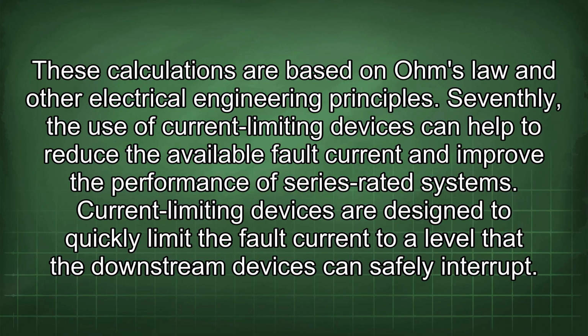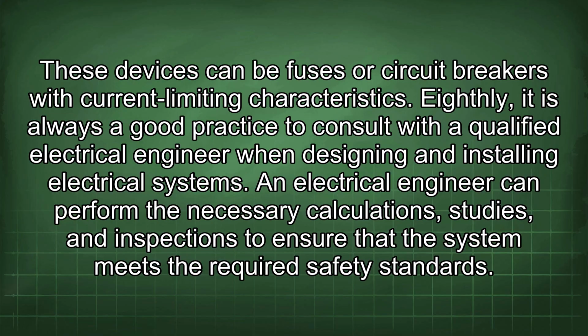Seventhly, the use of current-limiting devices can help to reduce the available fault current and improve the performance of series-rated systems. Current-limiting devices are designed to quickly limit the fault current to a level that the downstream devices can safely interrupt. These devices can be fuses or circuit breakers with current-limiting characteristics.